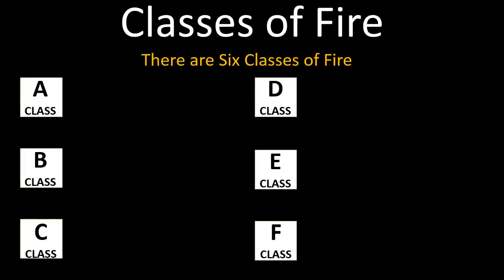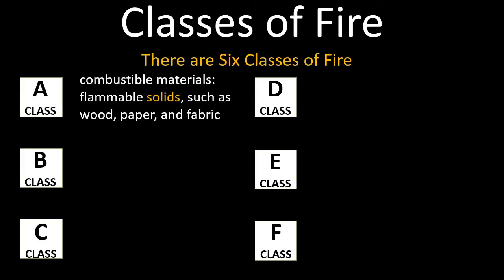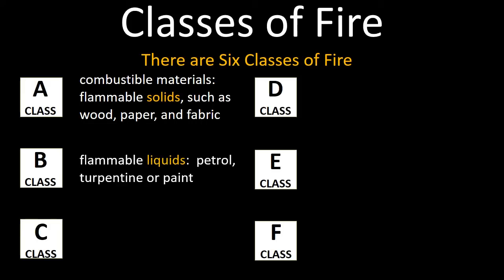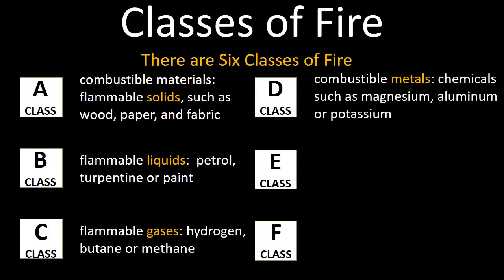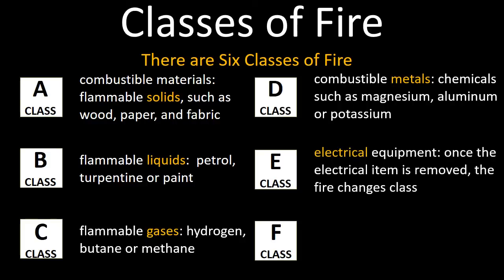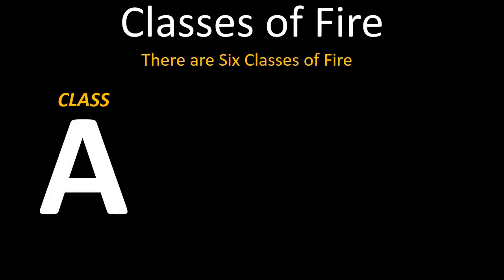There are six classes of fire: Class A, Class B, Class C, Class D, Class E, and Class F. Class A fire consists of combustible materials such as flammable solids, wood, paper, and fabrics. Class B includes flammable liquids such as petrol, turpentine, or paint. Class C includes flammable combustible gases such as hydrogen, butane, or methane. Class D includes combustible metals such as magnesium, aluminium, or potassium. Class E includes electrical equipment — once the electrical item is removed, the fire changes class. And Class F includes cooking oils, typically a chip pan fire.